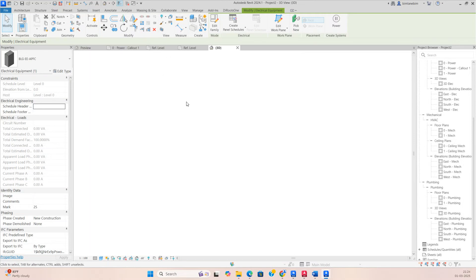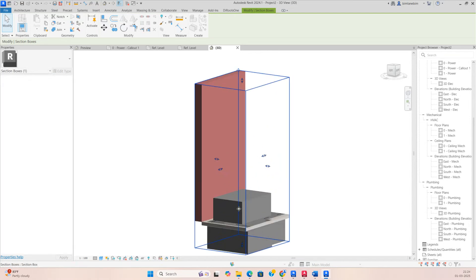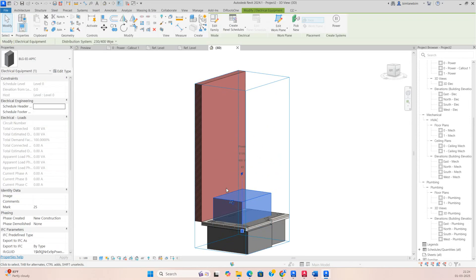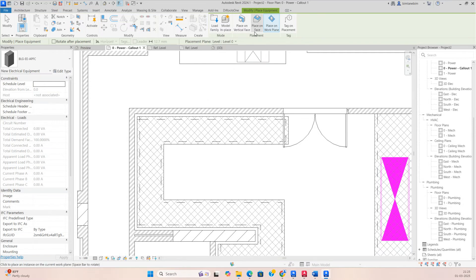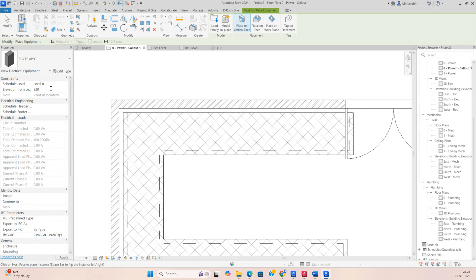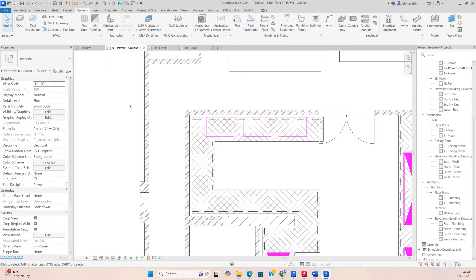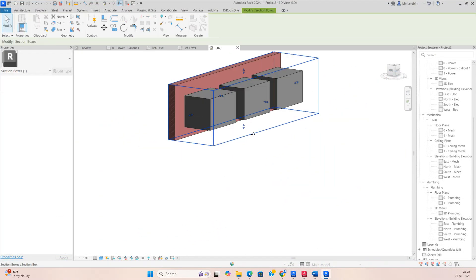Check in the 3D view — it was placing flat on the floor. Delete that one and go back to Electrical Equipment, then choose 'Place on Vertical Face'. Set the height to 1200mm and fix one panel here, another here, and another here. Go to the 3D view and you can see the APFC panels are fixed on the wall.